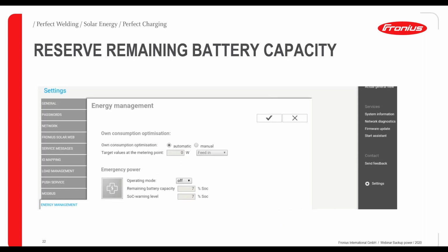Another thing you can do, you can reserve a remaining battery capacity. If you know that in this region or at this house there are many blackouts, many power cuts, then we would recommend as well to select a certain remaining battery capacity. So you can select here between 5 and 100%. You can choose here to reserve a specific remaining battery capacity in case of a blackout. But you also should know, when you do that, you cannot use this capacity for your standard operation, which is to supply the house at night, when the grid is on. So therefore, maybe don't go too high with these settings here. Maybe 20%, maybe 30% maximum.